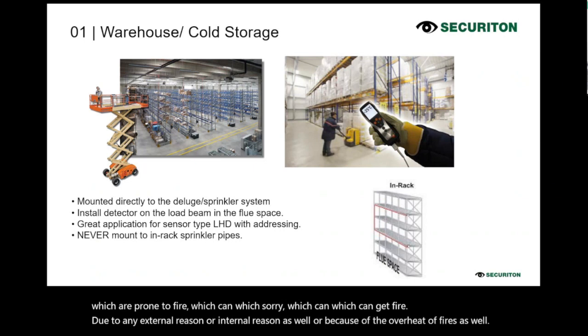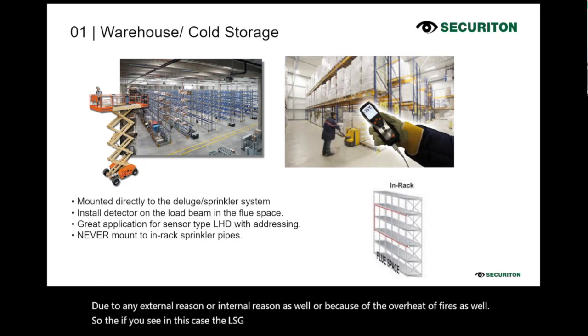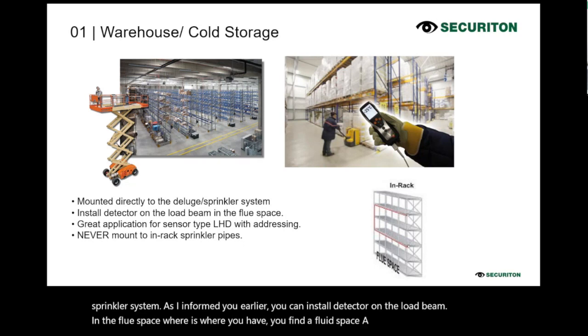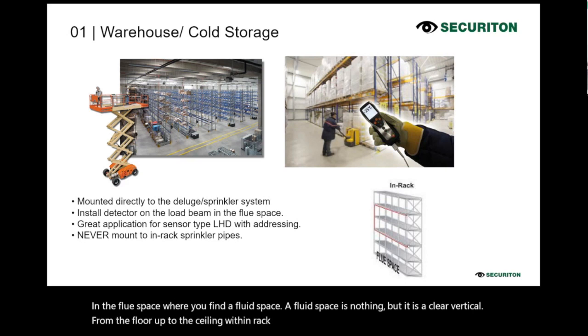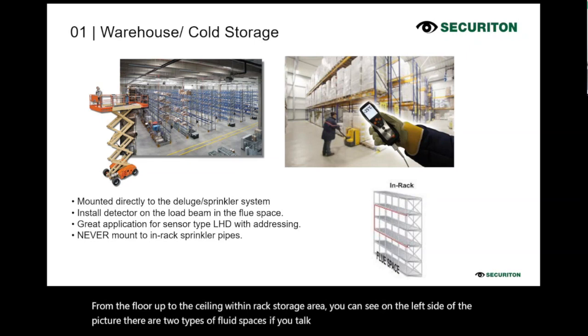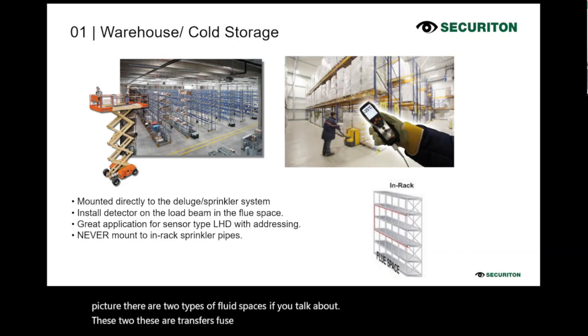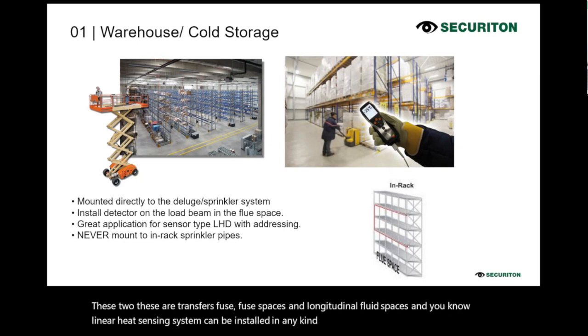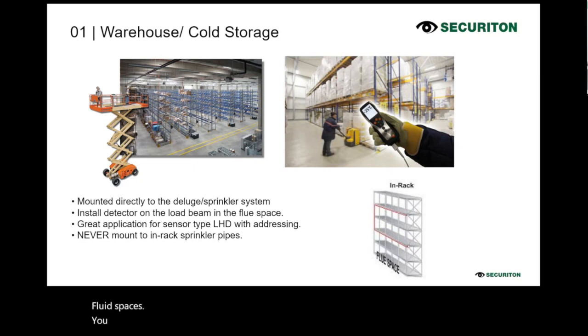So in this case, the LHD system can be mounted directly to the deluge or sprinkler system, as I informed you earlier. You can install the detector on the load beam in the flue space, where you find a flue space. Flue space is a clear vertical line from the floor up to the ceiling within the rack storage area. You can see it on the left side of the picture. There are two types of flue spaces: transverse flue spaces and longitudinal flue spaces. The linear heat sensing system can be installed in any kind of flue space. Please never mount these to the rack sprinkler pipes because it will disturb the efficiency.